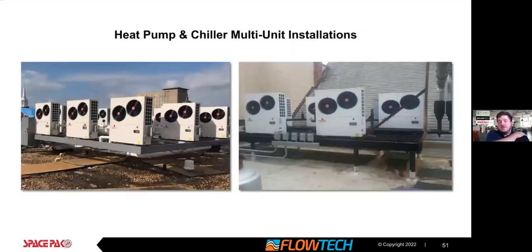Multiple unit applications. This is coming up more and more. Older picture here, but this was a church back east. I think they had a 2 million BTU boiler turning on. That's great on Sunday when everybody's in there and you have a high heating load, but not so good when the pastor's in on Wednesday and they're not using that much. So they replaced that with a stack of SpacePaks here, feeding a common supply and return loop, and it gives them much more efficiency, much more staging, and they were very happy with their installation.